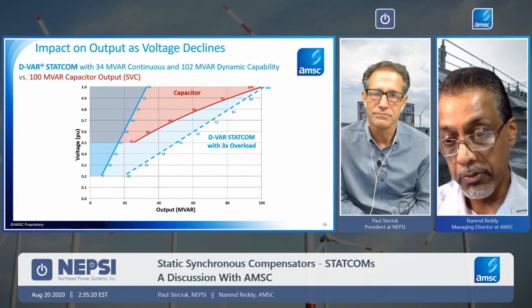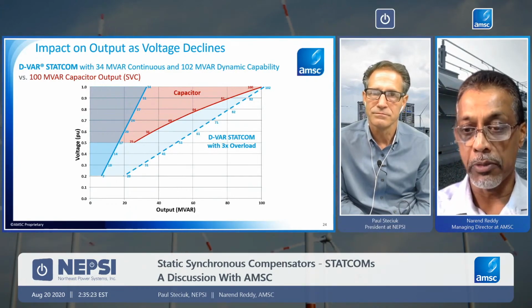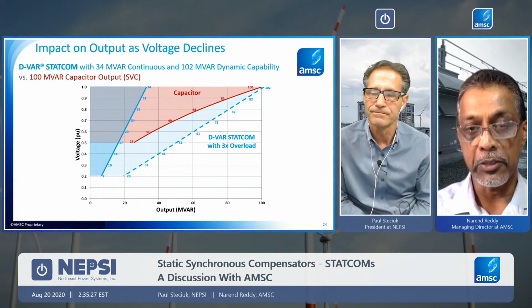If you need more steady state vars, we move into what we call the hybrid time frame, and that's where we can utilize capacitor banks that you supply. So what you're saying makes a lot of sense. Transmission level faults don't last that long. They're cleared very quickly, right? We have all kinds of relaying packages out there, pilot wire relaying and stuff like that, that clears faults very quickly. So having that 3 times rating for, I think you said 2 seconds, cuts down on the actual continuous rating that you need to purchase. So it cuts down on cost. It's a significant item to specify: what is the overload rating of the STATCOM and for how long can it go?